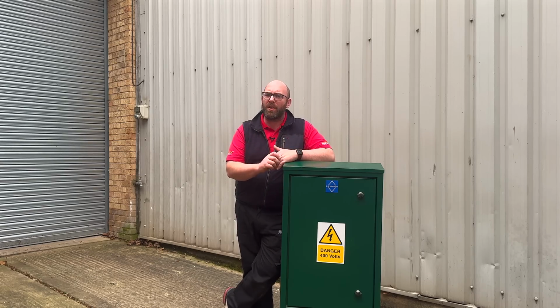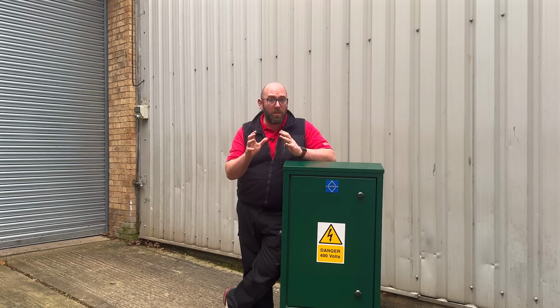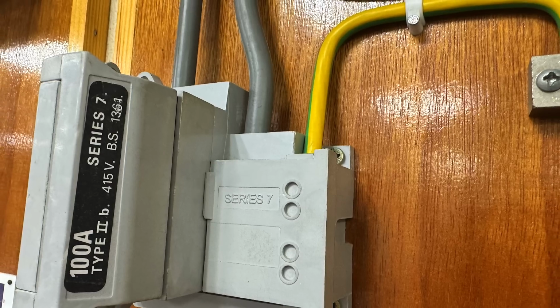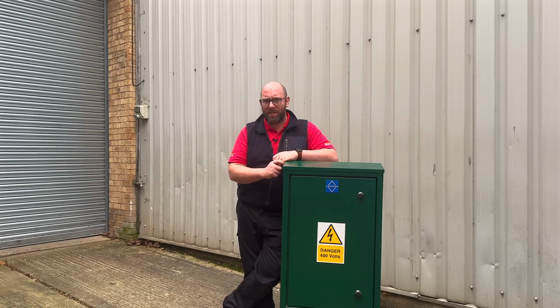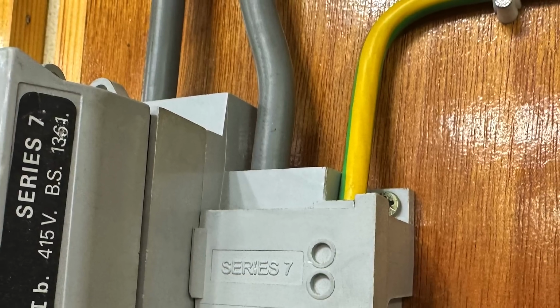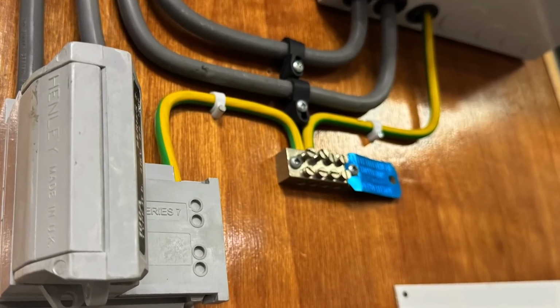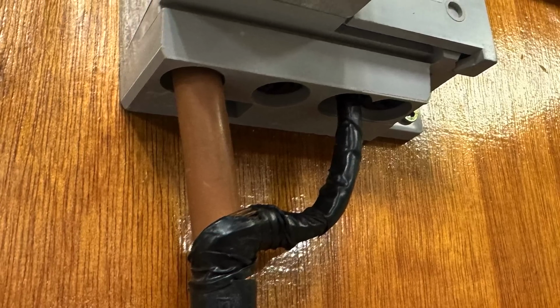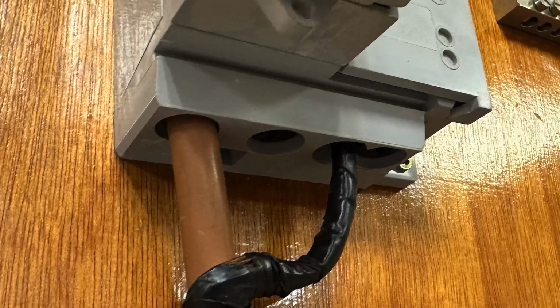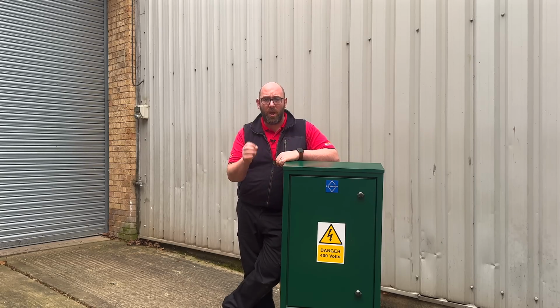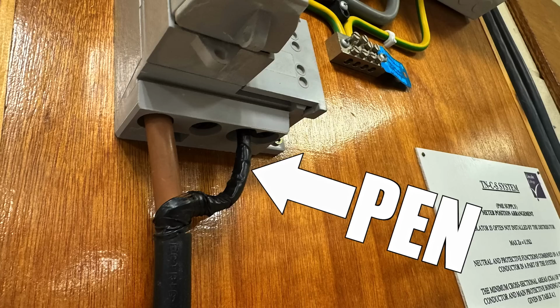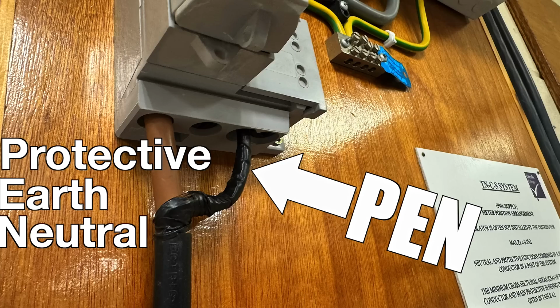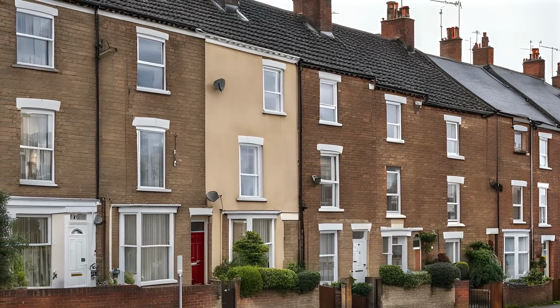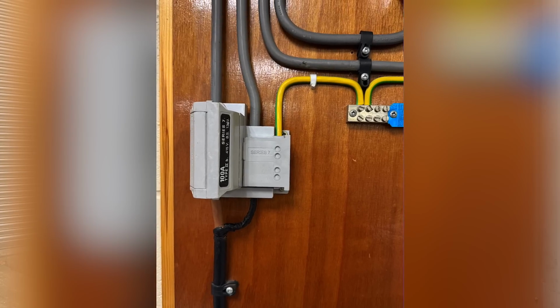But before we answer that question, let's remind ourselves of some of the terms we'll be using and what they mean, starting with a TNS and a TNCS. TNCS stands for Terra Neutral Combined and Separated. What this means is that in certain parts of the system, the neutral and earth conductors are combined and then separated for the final distribution to the premises. One of the reasons this is done is because it's cheaper, as we're only running two conductors from the substation, the line conductor and the combined neutral earth conductor. This is what we call the PEN conductor, short for protective earth and neutral. As the system branches out to individual buildings, such as your home, it splits into separate earth and neutral conductors.